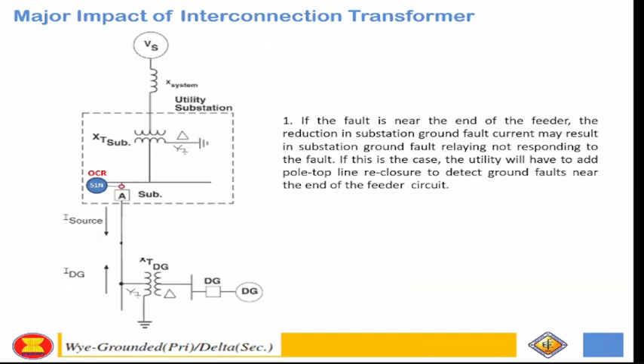So, another case. If the fault is near the end of the feeder, the reduction of substation ground fault current may result in the substation ground fault relay not responding to the fault. Okay? And if this is the case, the utility has to add a pole-top recloser to detect ground faults near the end of the feeder. This means that if there is a fault at the end load, in the zero sequence network, the DG transformer and the DG at the utility substation share the fault current, or there is a redistribution of fault current. Thereby, your protection, the feeder and breaker A, becomes insensitive.